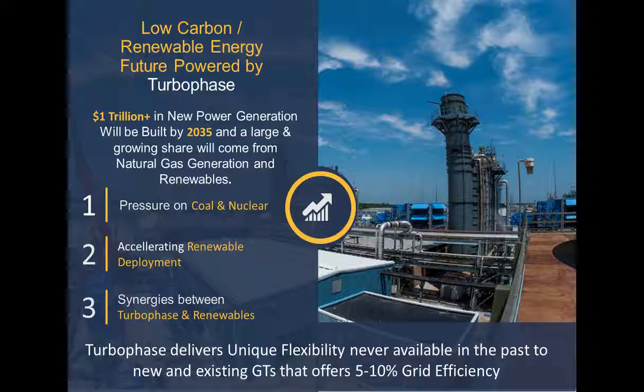So, why we created Turbophase. This was a product we invented in 2012. Patents were complete in 2013, and our first install was in 2014. The whole genesis behind Turbophase was to allow more renewable penetration into the grids, using your existing combined cycle and simple cycle gas turbines to support that renewable deployment. And that means they have to get more flexible. Today's combined cycles have long start times, they are difficult to ramp, and the start cost to owners is high. And with simple cycles, 10 minutes is not fast enough for a start time. So we brought Turbophase to provide the benefits of a flexible peaking simple cycle power station at battery speeds, but at combined cycle efficiencies. That was the whole genesis of why we started down the path with Turbophase.